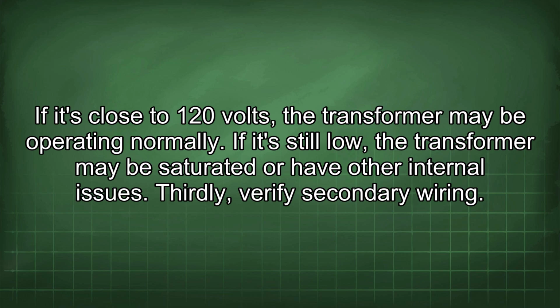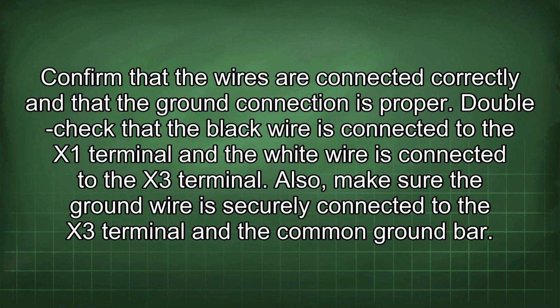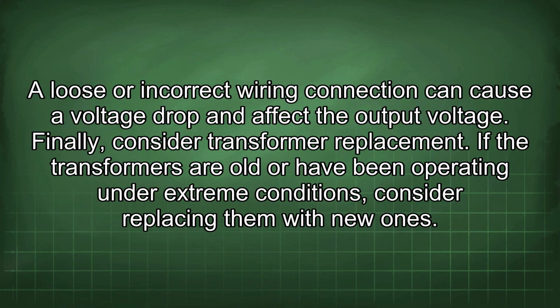Thirdly, verify secondary wiring. Confirm that the wires are connected correctly and that the ground connection is proper. Double-check that the black wire is connected to the X1 terminal and the white wire is connected to the X3 terminal. Also, make sure the ground wire is securely connected to the X3 terminal and the common ground bar. A loose or incorrect wiring connection can cause a voltage drop and affect the output voltage.